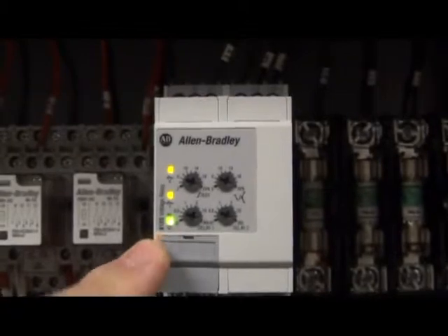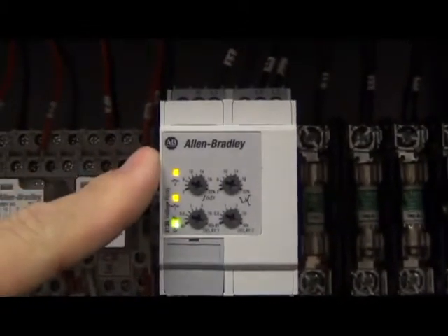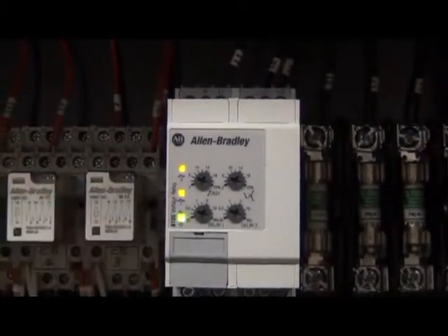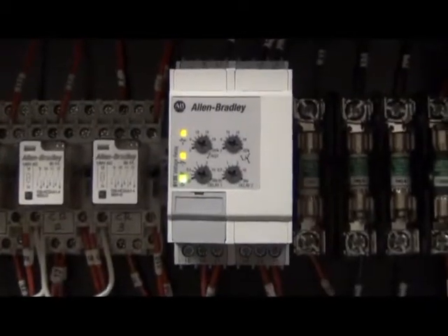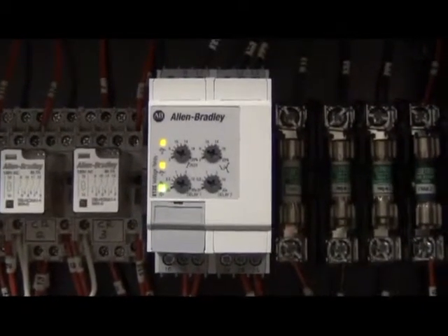As you can see, we now have a green LED indicator and two amber LED indicators, and this is the correct configuration. Now we know that the phase is correct.